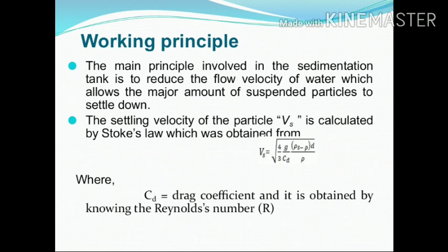Now let us see the working principle of the sedimentation tank. The main principle is to reduce the flow velocity of water, which allows the major amount of suspended particles to settle down; the velocity at which a particle settles is known as settling velocity. The amount of suspended particles collected at the bottom depends on factors like shape and size of tank, size of particle, temperature of water, flow velocity, detention period, etc. The settling velocity vs is calculated by Stokes' law: vs = √(4g(ρs − ρ)d / 3Cd·ρ).